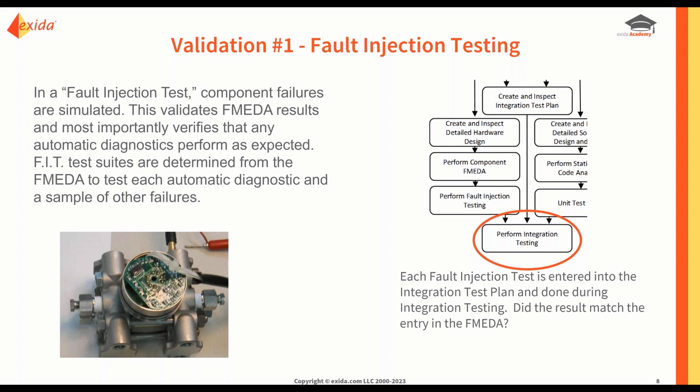This could be a very time-consuming process, but imagine a device with 200 components and about five automatic diagnostic functions. You would certainly pick five for the automatic diagnostics and maybe another five or ten others — so somewhere in the range of 10 to 15 fault injections. That's not too bad; it can easily get done in a half day, worst case a whole day if there's a lot of setup. With good planning and careful sequencing, you can get through a fault injection test in a few hours.